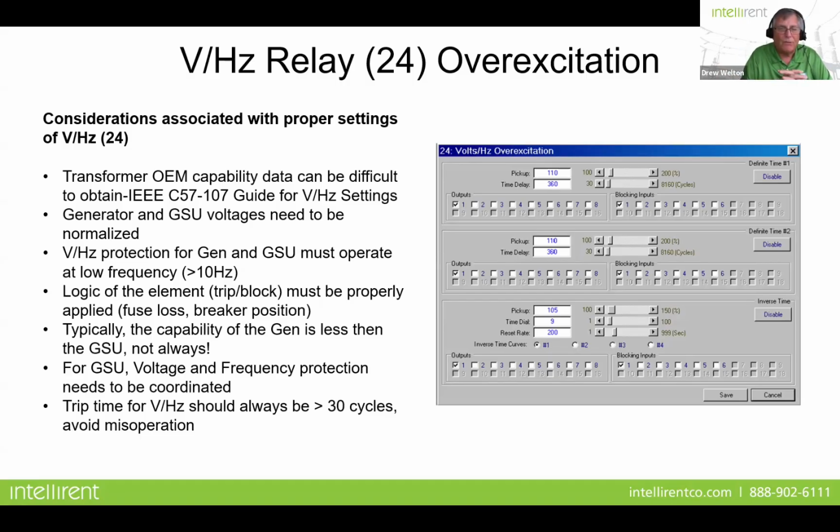They're kind of interesting elements. They have to operate at a low frequency because it has to be able to protect the generator as it's coming up to speed. And typically the capability of the generator is less than the GSU in terms of what it can withstand. It could go hand in hand. They could be identical. One could withstand more than the other. But what's important here is that we make sure we set these properly according to IEEE standards.